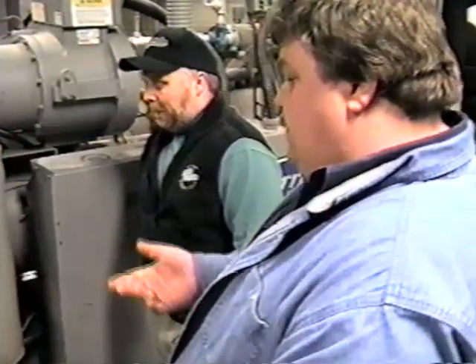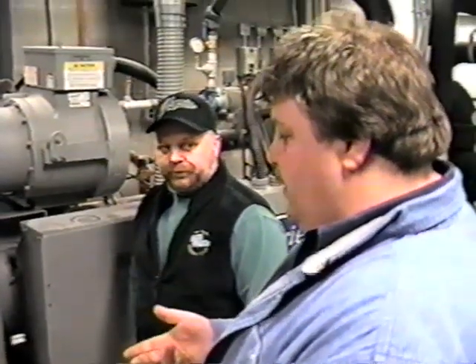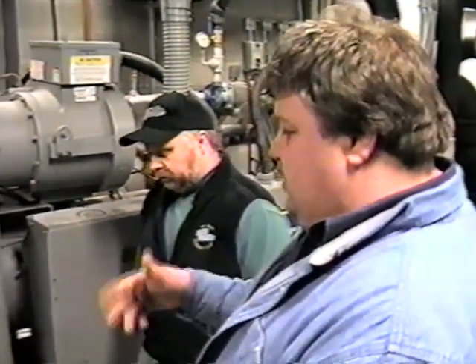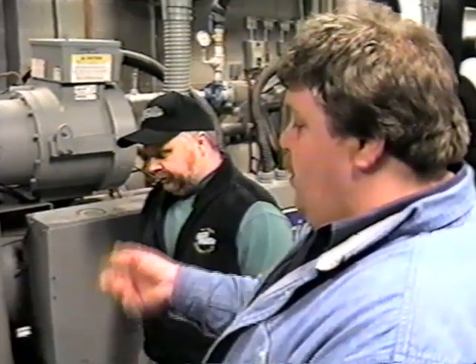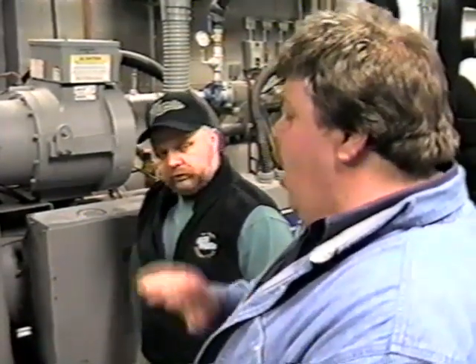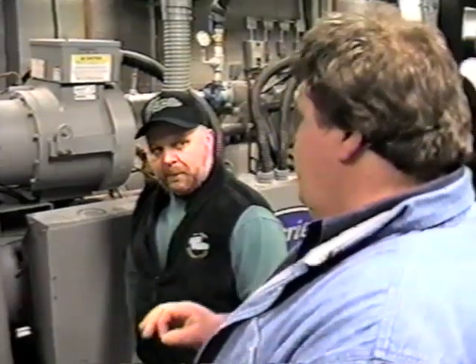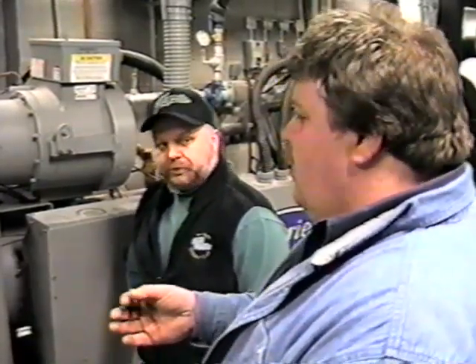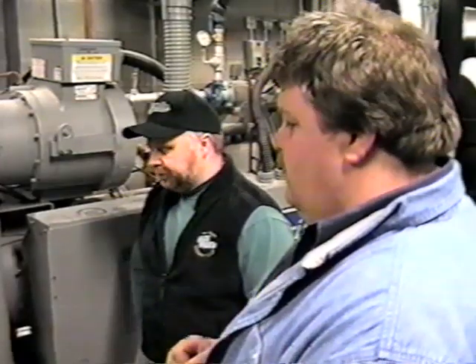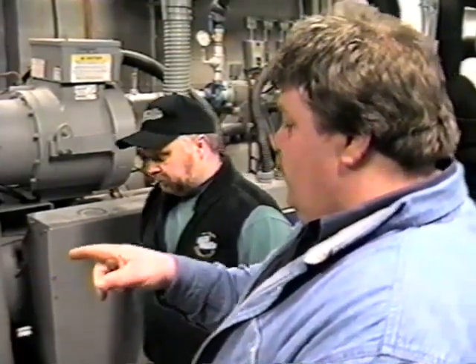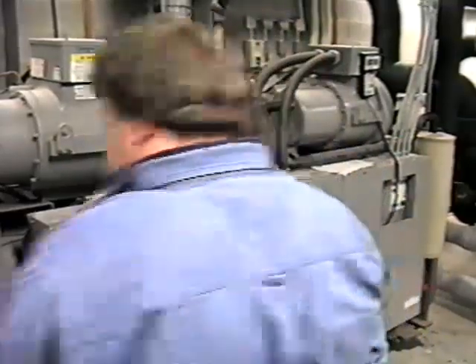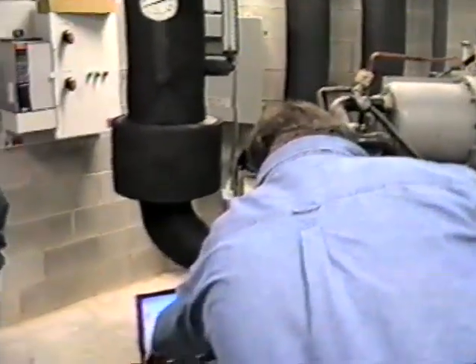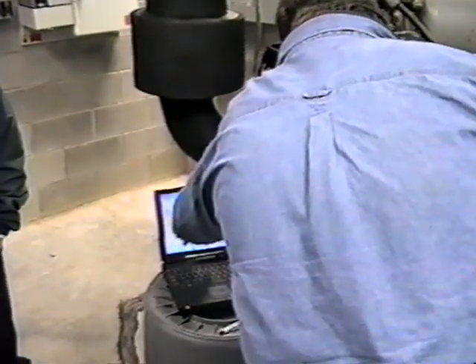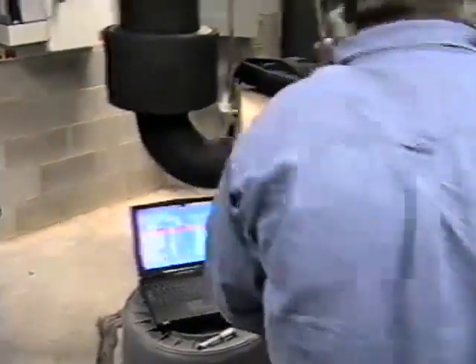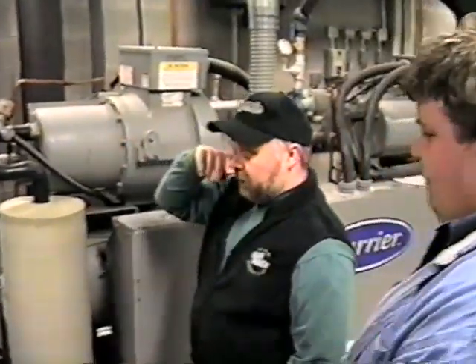So that's pretty much the pump on, pump off. When it satisfies, the pump will shut off all the way, and after a time delay, it'll go back to the low speed because you can't just transition right off like that. When that happens, you're going to see the chiller start go to stop. Your pump speed will be low, and your readback will be low. This is basically what will be on that readout right there.